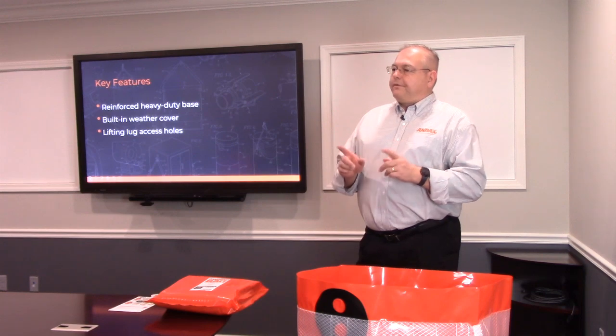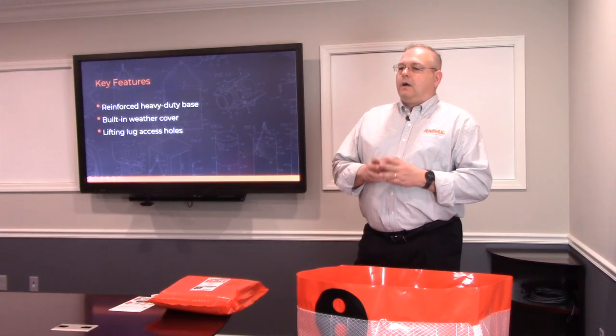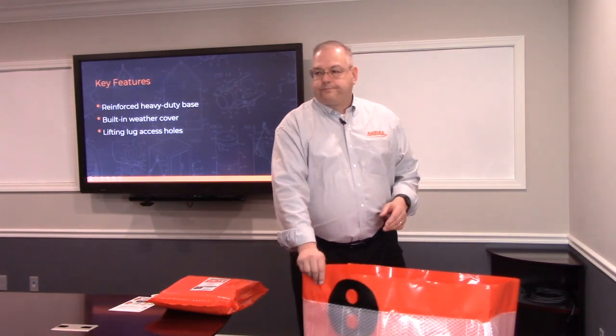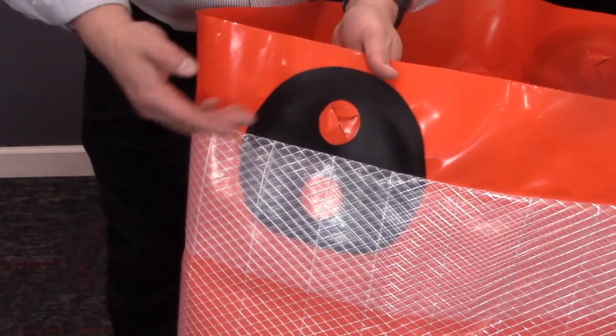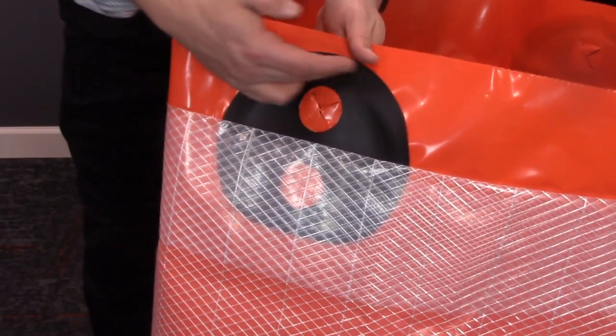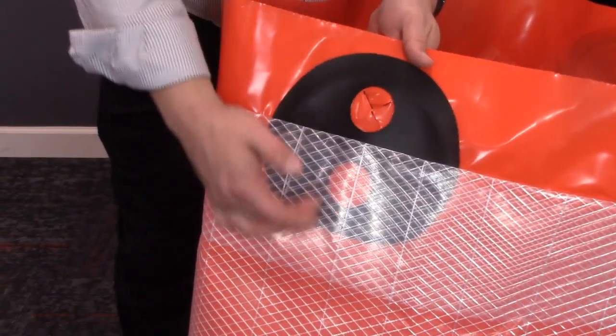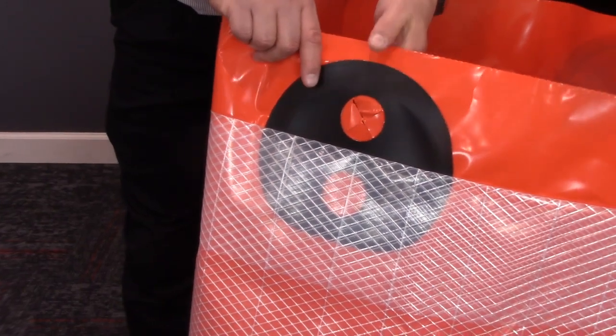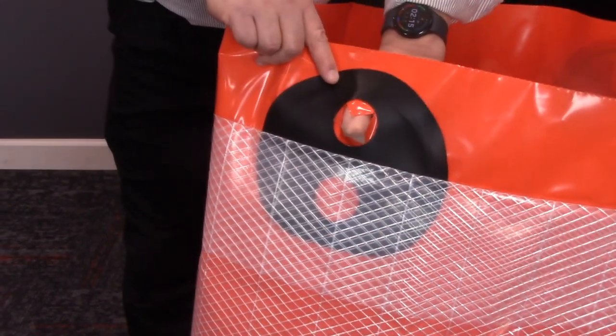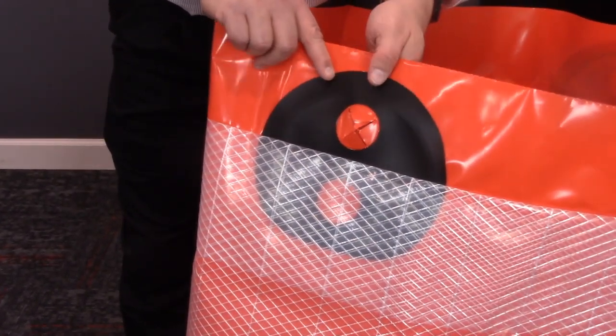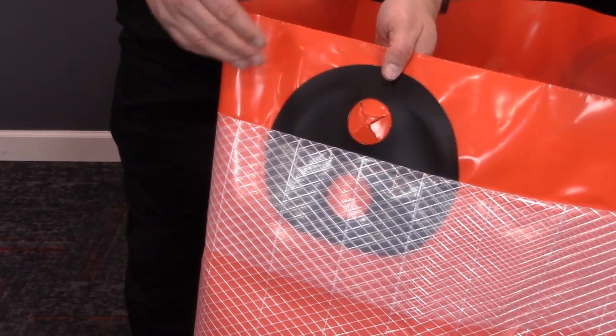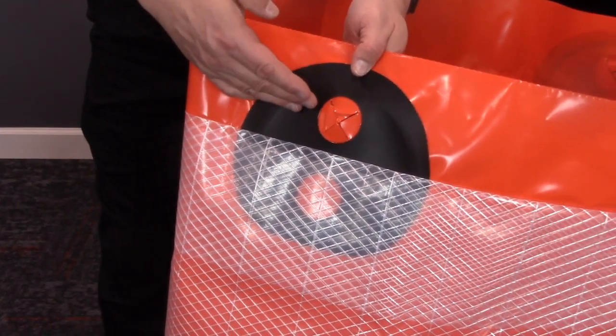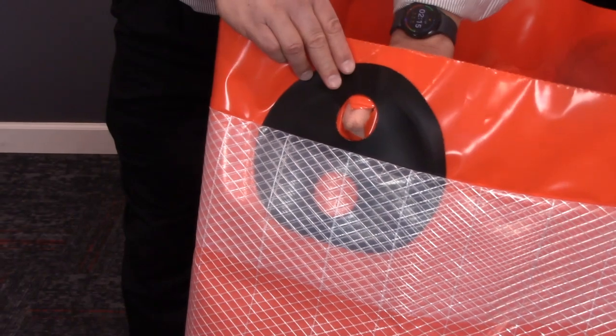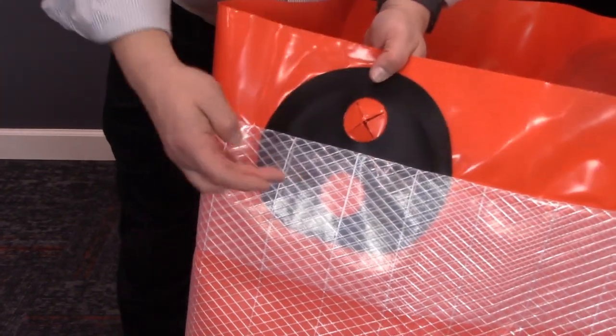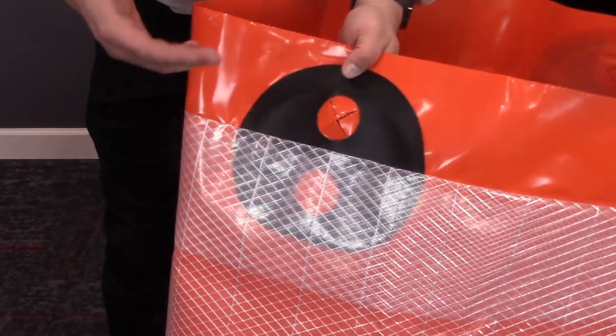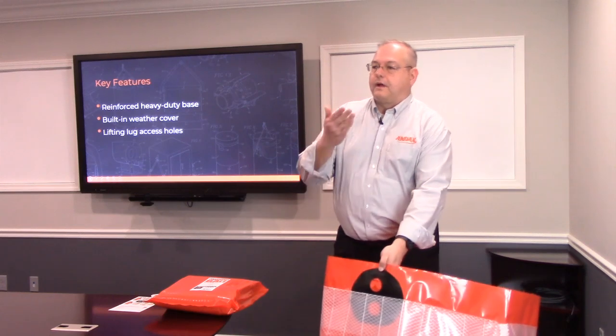The most important feature of the TCB are the lifting lug access holes. These access holes allow you to reach the transformer manufacturer's lifting lugs once the transformer is contained inside the bag, ensuring your OSHA compliance. The top set of transformer lugs are accessible when the weather cover is down. The second set are accessible when the weather cover is deployed.